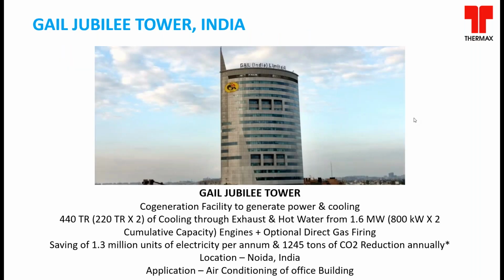Another important example is the GAIL Jubilee Tower located in Noida. This entire complex runs on a CHP model, with 2 800 kilowatt gas engines, where the exhaust and jacket water are routed through an absorption chiller catering to a majority of the building's cooling requirement, with the rest handled by electrical chillers.